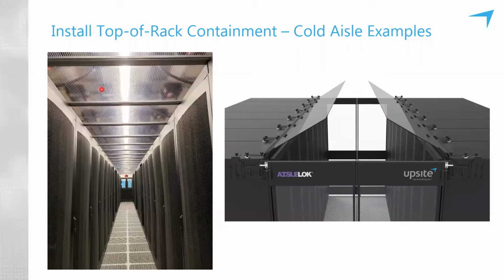So from a fire suppression standpoint, this works well in most all environments and is supported with your local jurisdiction because these panels or the inserts will flutter out of the frames before the sprinkler system goes off. And we're talking like way less than a pound each. These are like leaves falling off the tree in the fall.